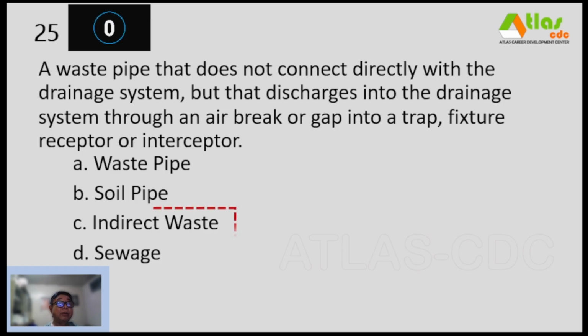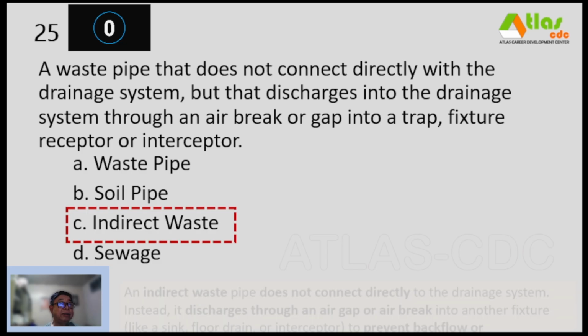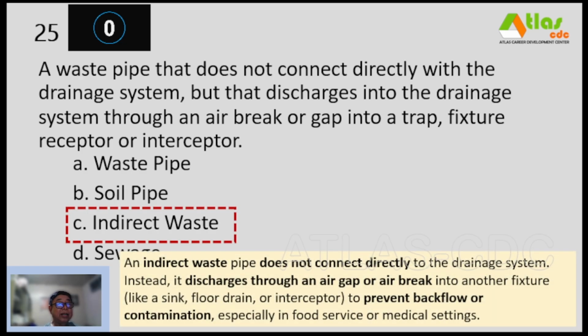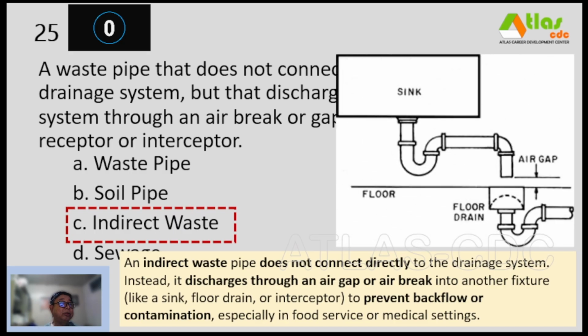And our correct answer is letter C, indirect waste. So an indirect waste pipe does not connect directly to the drainage system. Instead, it discharges through an air gap or air break. Ito yun. So hindi karugtong talaga. Mayroong air gap. Into another fixture, ayan, like a sink or drain or interceptor, to prevent backflow or contamination, especially in food service or medical setting. So parang nakahiwalay siya talaga, no?